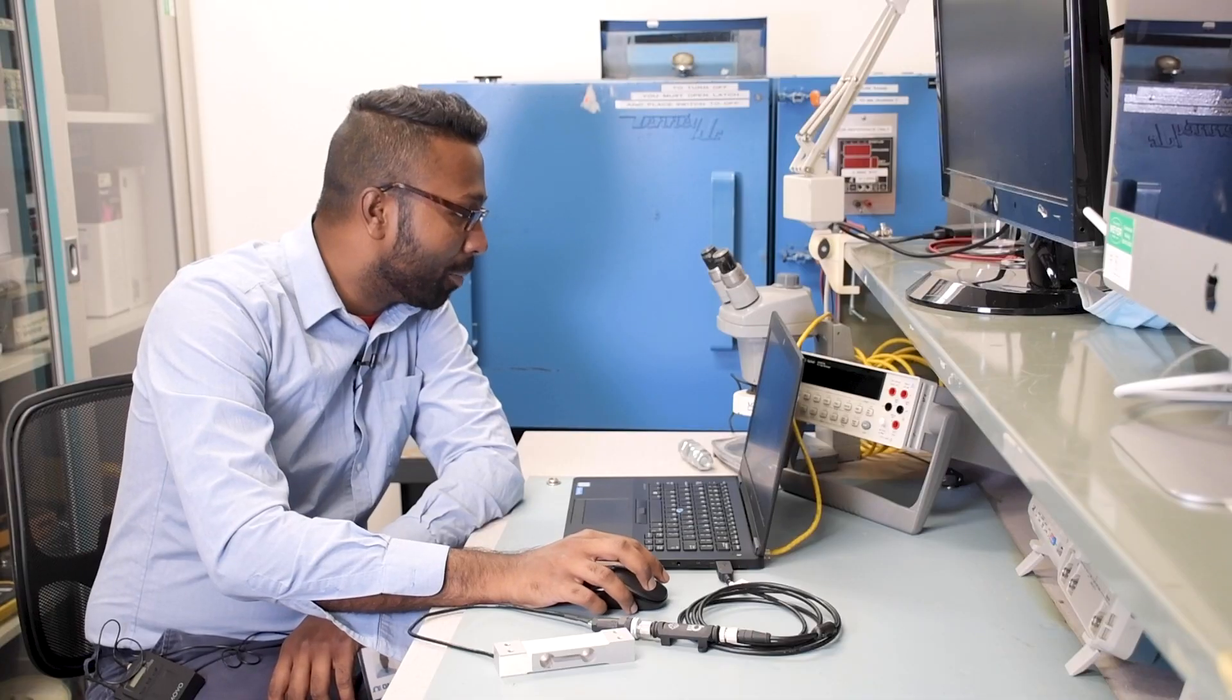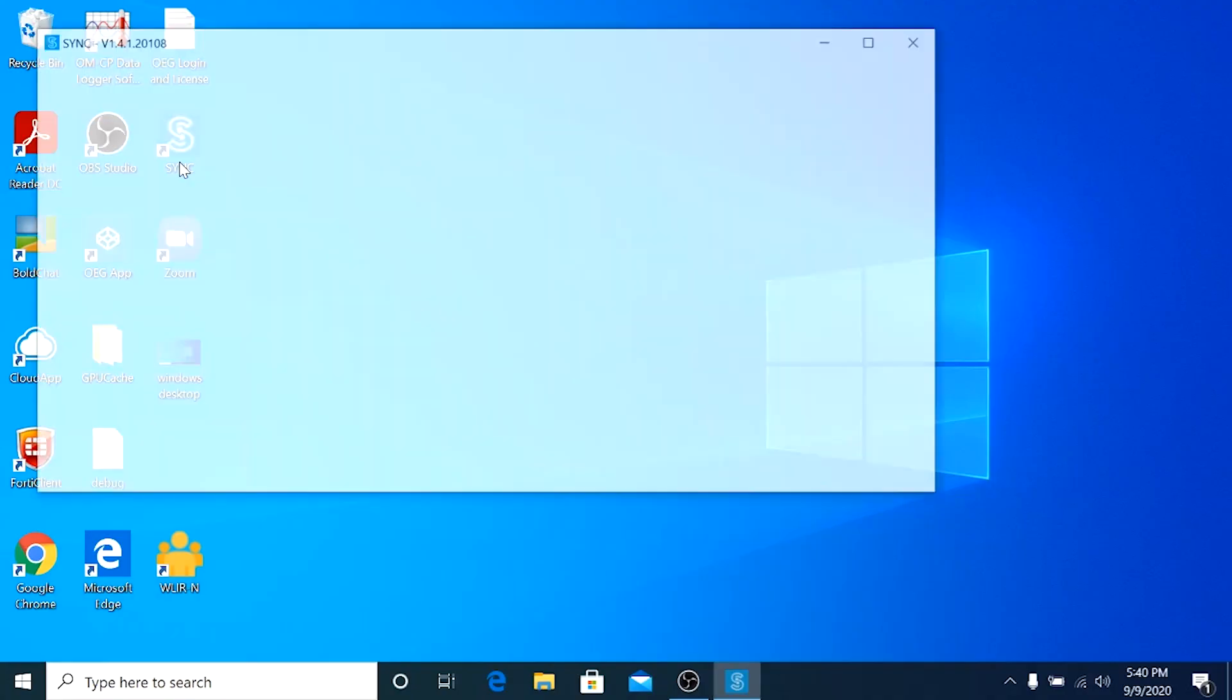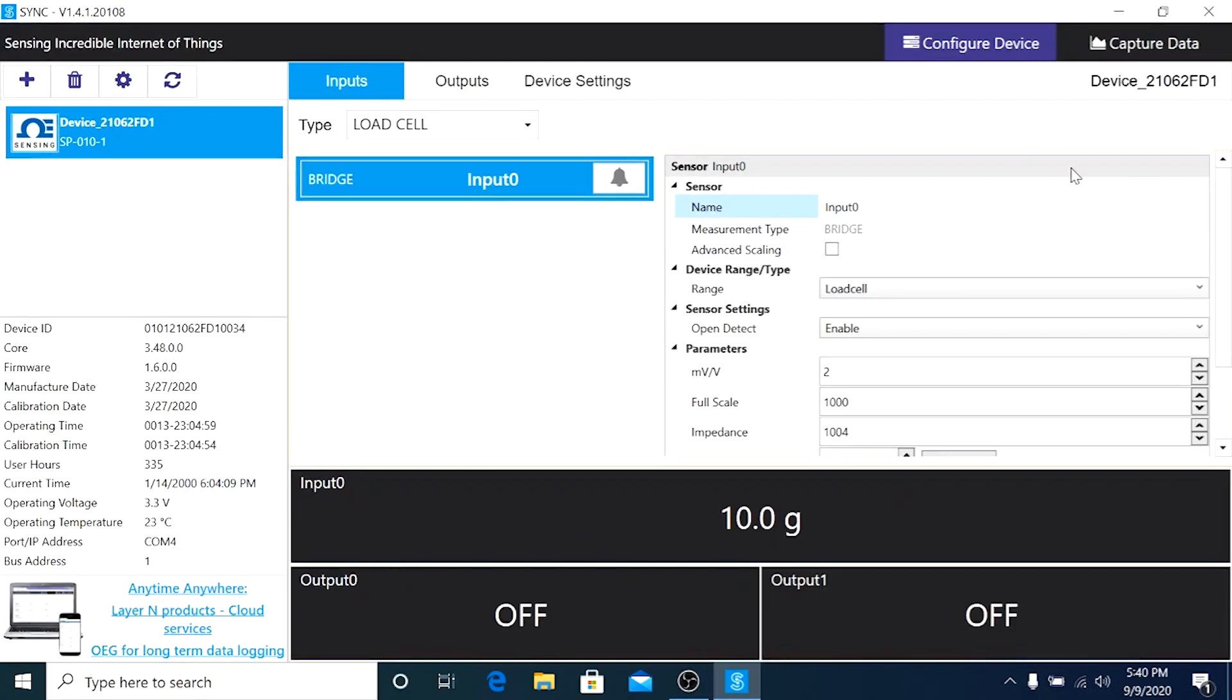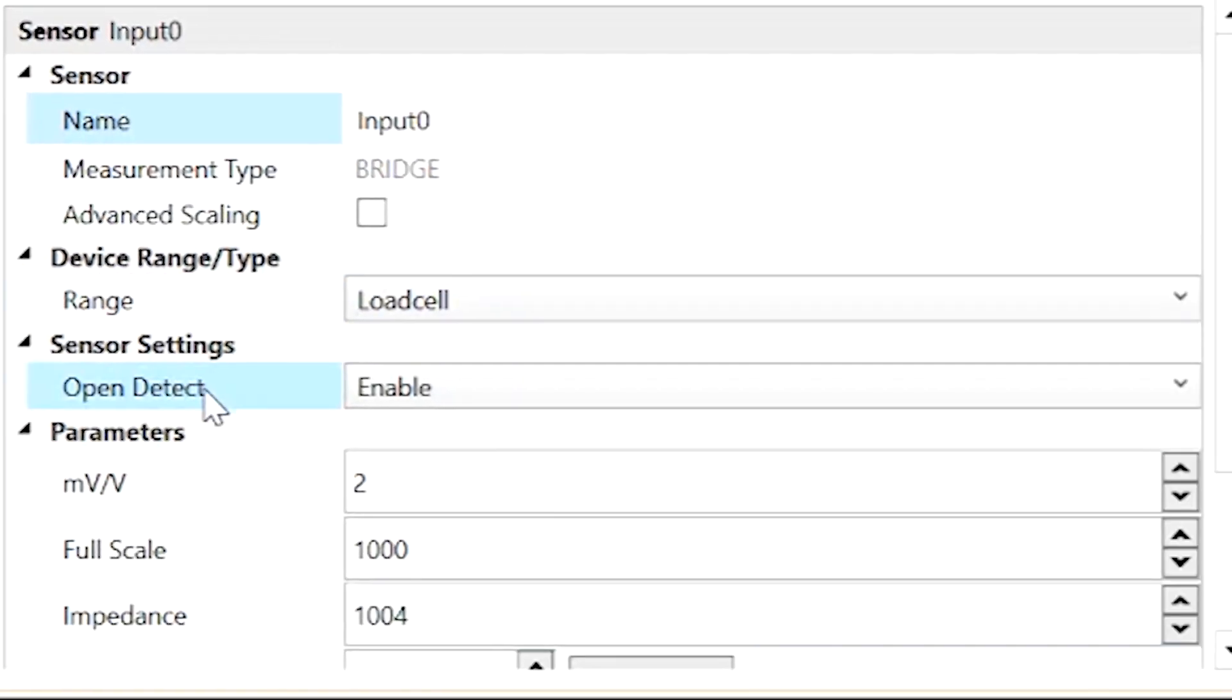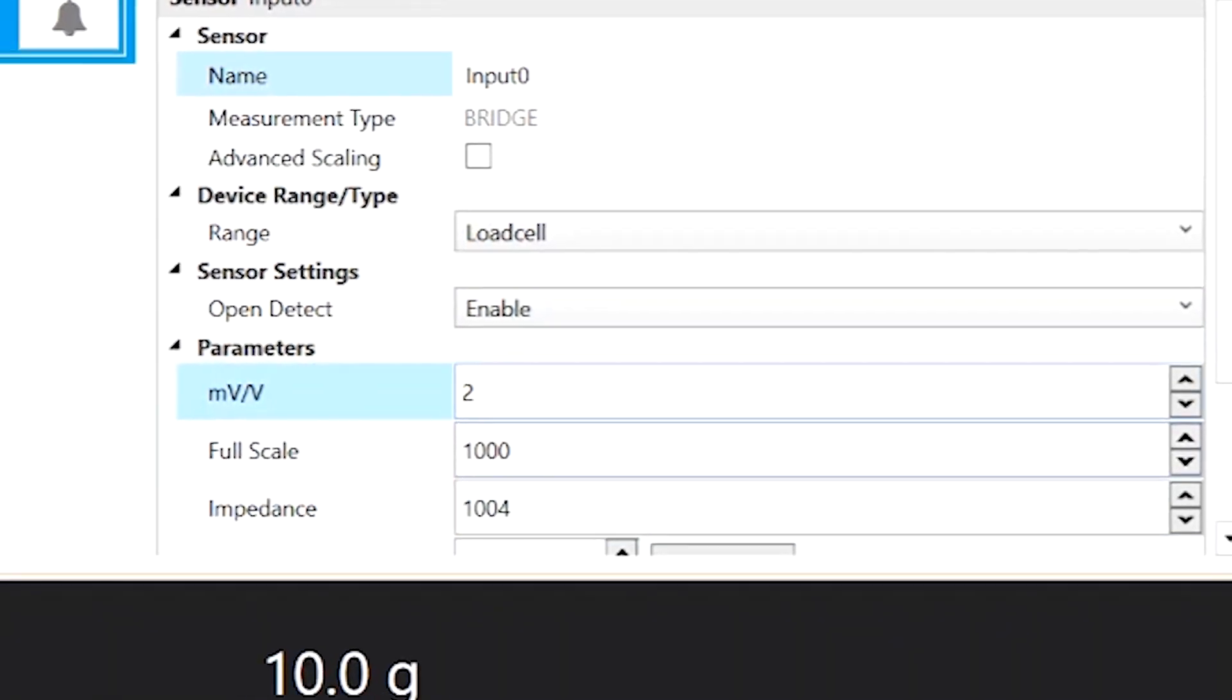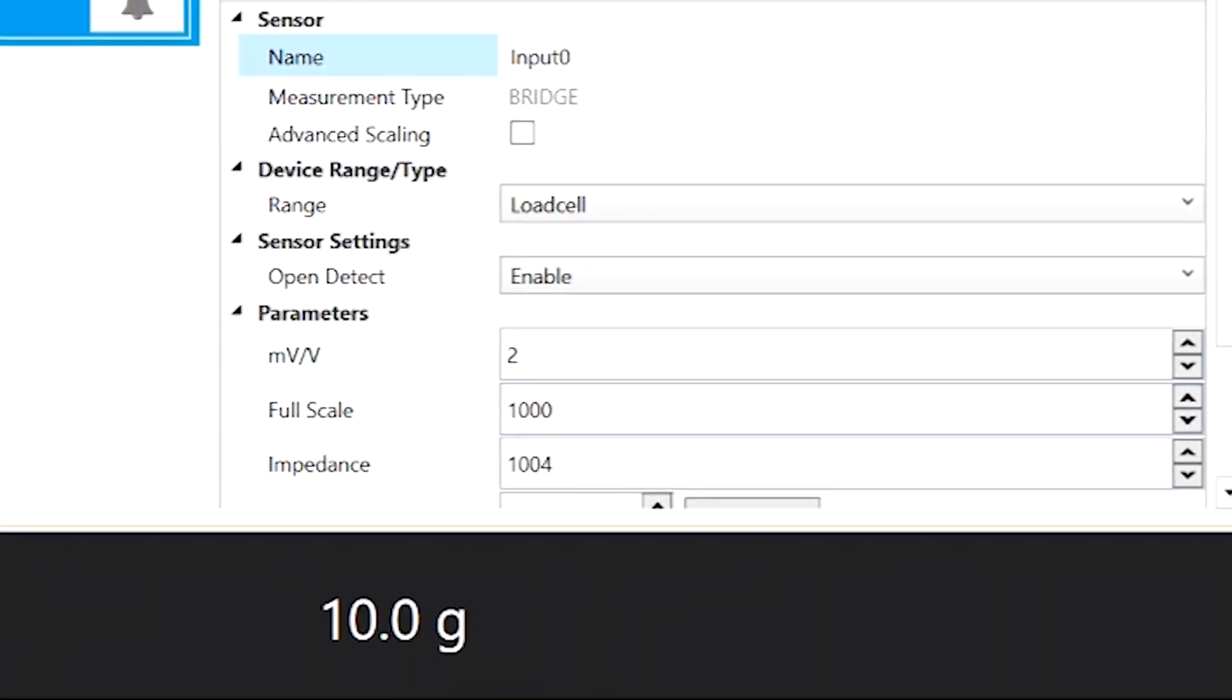Let's launch the Omega Sync software. As soon as you launch it, you should see the type listed as load cell and the range is load cell, with open detect as enable. The only thing we need to change are the parameters and the units if needed. Take the calibration certificate that comes with the load cell and look at the sensitivity.